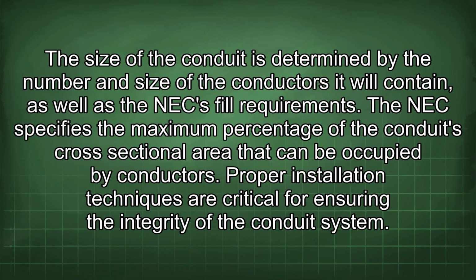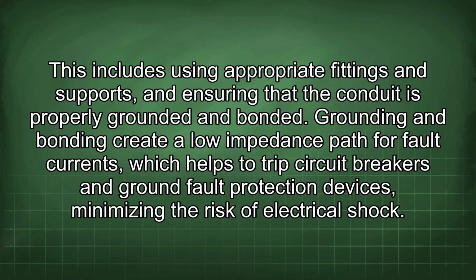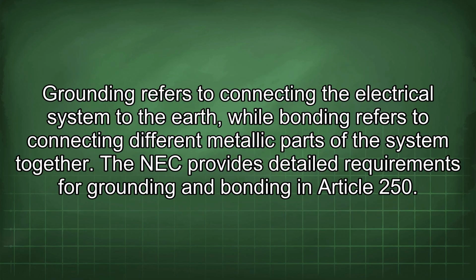Proper installation techniques are critical for ensuring the integrity of the conduit system. This includes using appropriate fittings and supports, and ensuring that the conduit is properly grounded and bonded. Grounding and bonding create a low impedance path for fault currents, which helps to trip circuit breakers and ground fault protection devices, minimizing the risk of electrical shock. Grounding refers to connecting the electrical system to the earth, while bonding refers to connecting different metallic parts of the system together. The NEC provides detailed requirements for grounding and bonding in Article 250.